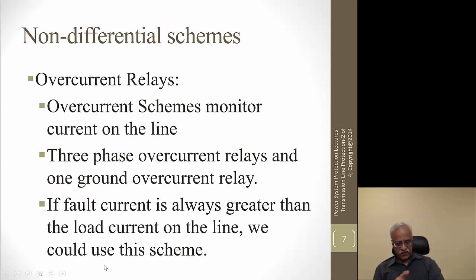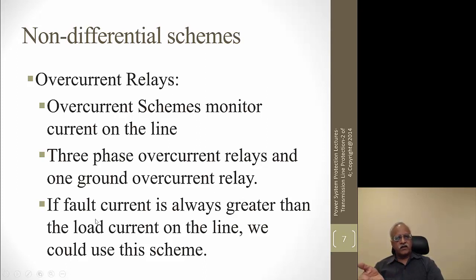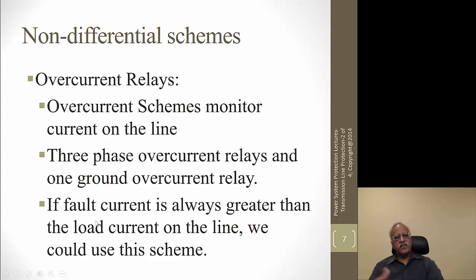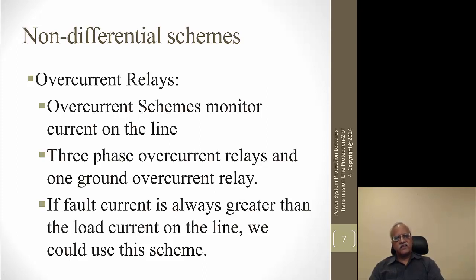In an interconnected network, directional overcurrent relays are used. Ground overcurrent relays are very useful because under normal conditions Ia + Ib + Ic equals zero, so there is no ground current. Under ground fault conditions that current appears, and we can set directionality looking towards the line. In radial feeder systems, non-directional overcurrent relays suffice, whereas in a transmission system with an interconnected network, directional relays are required.